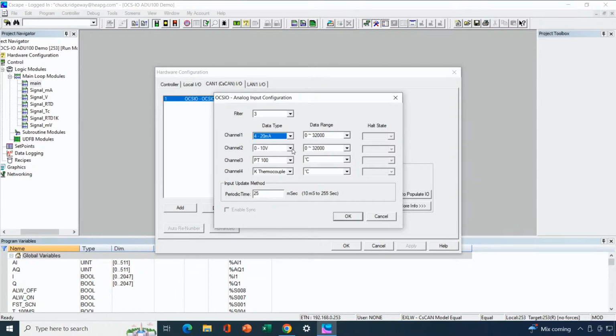So let's take a look at all those different signals that are available here. I'll just pull one of these down, and on the screen I've got voltage and a couple of different current options, 0 to 60 millivolts for load cells, and all those different thermocouple types. A couple of different RTDs, and of course disabling the channel altogether, because disabled channels will not be scanned, just so you know. Once you select the particular signal or sensor type, then you can select a data range.